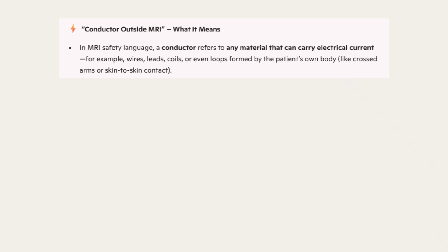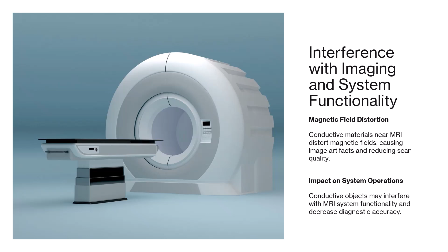Conductive materials near the MRI scanner can distort magnetic fields, leading to image artifacts and degraded scan quality. Additionally, they may interfere with system operations and diagnostic accuracy.